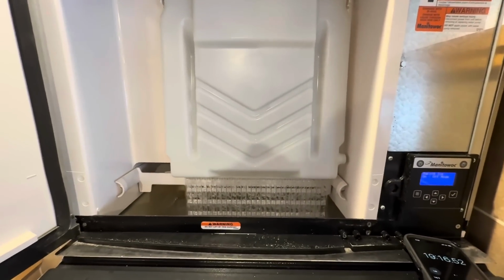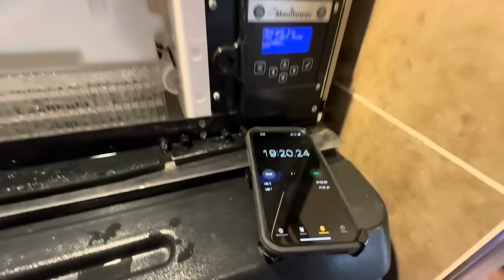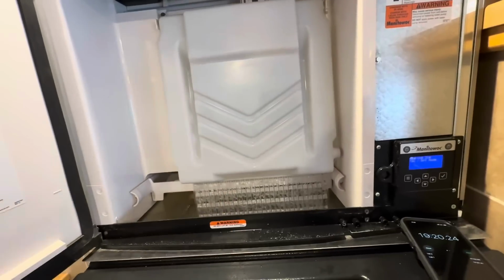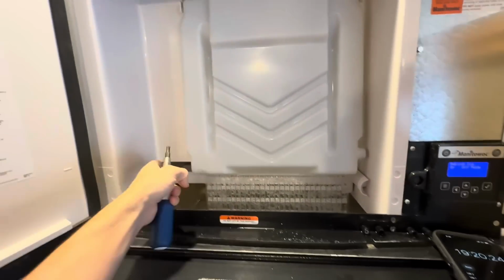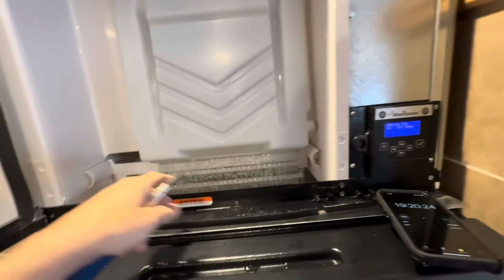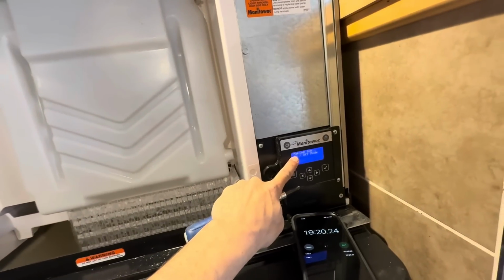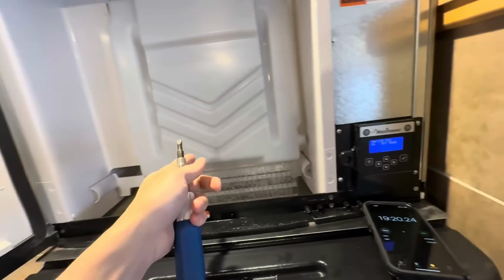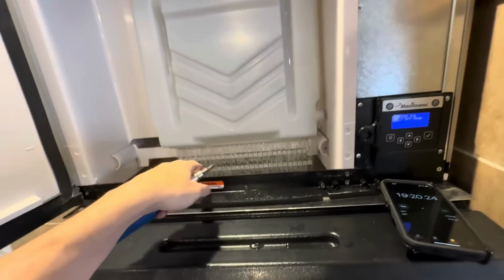Barely caught that. Ice just fell from the evaporator. Harvest time was about 1 minute and 52 seconds. The machine will end up shutting off because the water curtain is held open. That'll go from making ice to full bin. Like I said, 30 seconds and it'll shut off.